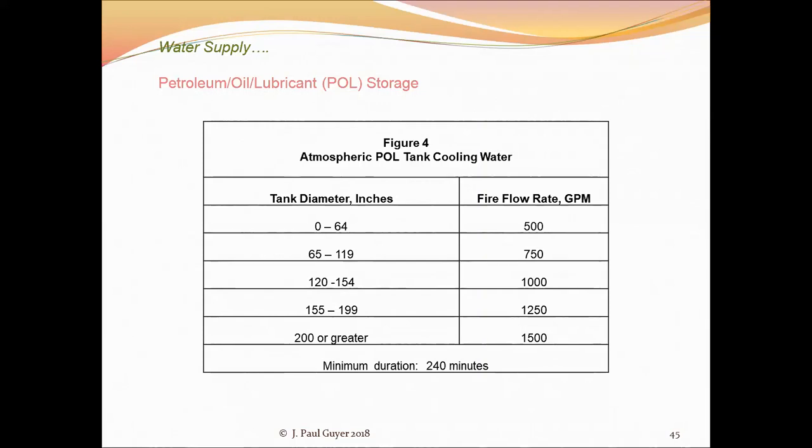The point here with fuel storage tanks is that the fuel is lighter than the water, and the only thing that is burning is the top layer of the fuel in the fuel tank. So it's irrelevant how much fuel there is down in the tank below the top surface. It's that top surface area that is the threat, if you will.